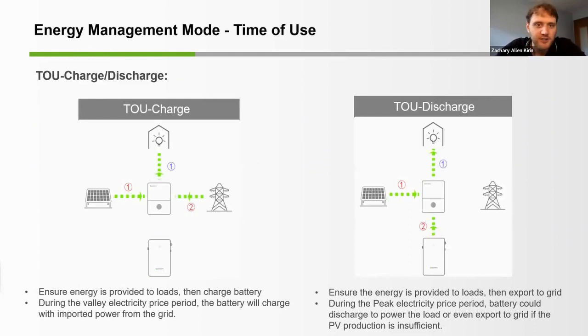The time of use charge is the next mode, and this is also very important. Again, very important for California, some states in New England. The time of use charge and discharge mode ensures that energy is provided to the loads first. If needed, energy will be imported from the grid at a configurable time to charge the battery. This might be one of the lower use functions, the time of use charge, but time of use discharge, the energy for the loads is ensured first, then the PV production or stored battery energy can be exported to the grid at certain times that have been delegated by the customer.